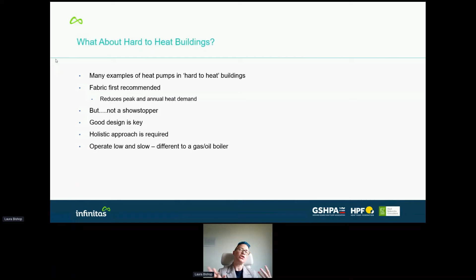Another consideration with hard to heat or existing buildings is to operate the heat pump differently - low and slow. A gas boiler typically comes on with a big boost in the morning, warms the building quickly, peters off during the day, then has a second boost around 4 o'clock or so. Don't do that with a heat pump. Best to leave it running all the time in the background. With these older buildings, thermal mass helps because it keeps the heat in. So operating low and slow is the way to go, particularly in existing buildings.